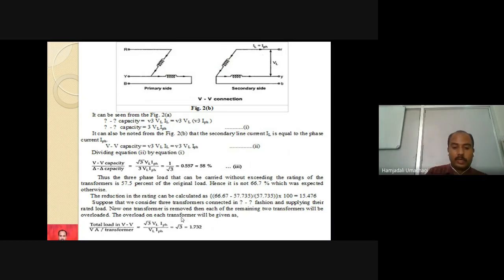To calculate the overload on each transformer, it can be calculated as total load in VV divided by volt-ampere per transformer. So what is the total load in VV? Just now we have calculated that VV capacity is √3 times VL IPH. So total load is √3 times VL IPH, and volt-ampere per transformer is VL IPH. So VL IPH gets cancelled, and the remaining is √3, which is 1.732. Now from this expression we can see that 1 indicates its own loading capacity, it is going to carry its own load, and the remaining 0.732 is the overloading.